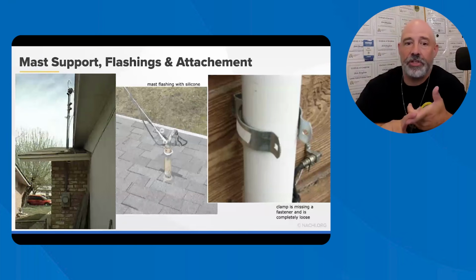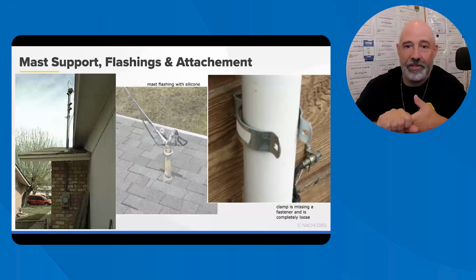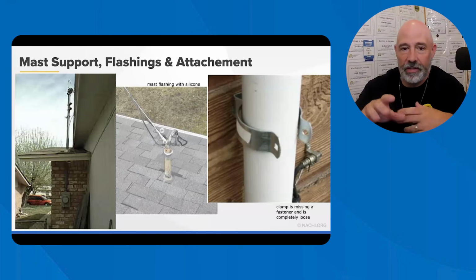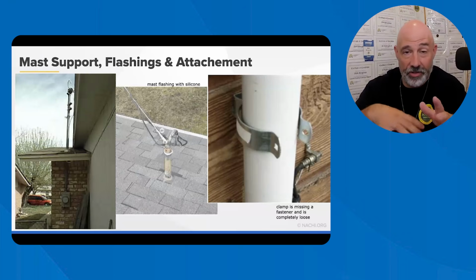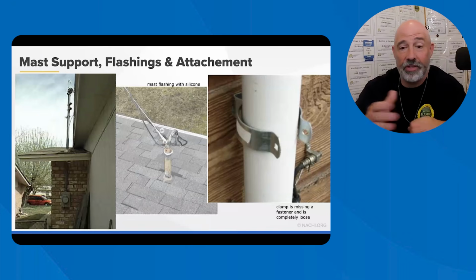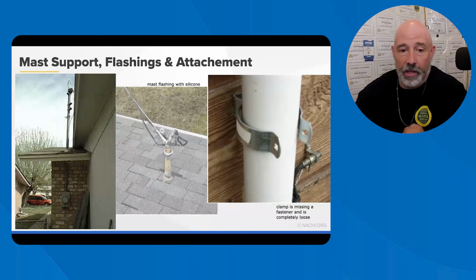So the IRC is silent on the size requirement and conduit type to be used for the mast or the riser. It's also silent about height above the roof. It can extend before being supported by braces or guy wires in many jurisdictions. You might want to just look where you're actually inspecting.